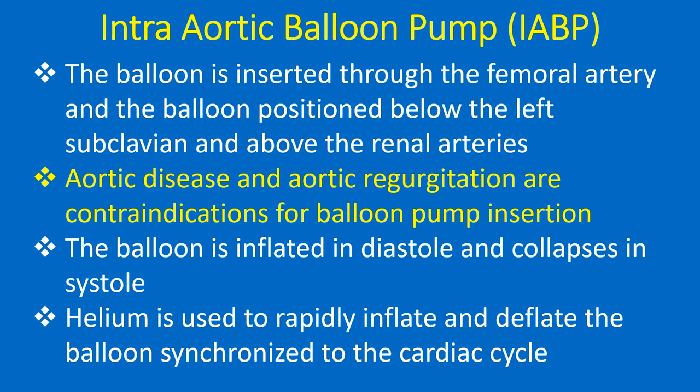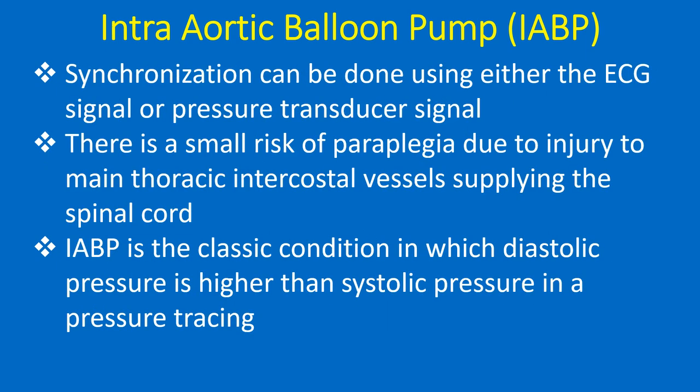The balloon is inflated in diastole and collapses in systole. Helium is used to rapidly inflate and deflate the balloon, synchronized to the cardiac cycle. Synchronization can be achieved using either the ECG signal or a pressure transducer signal.